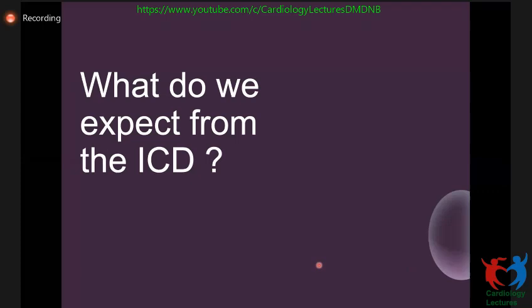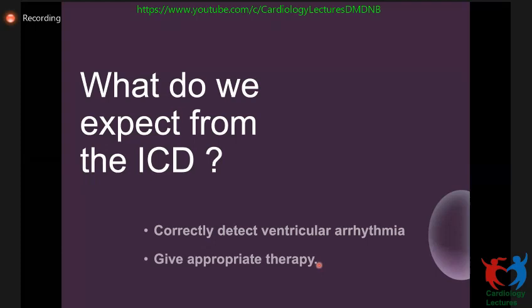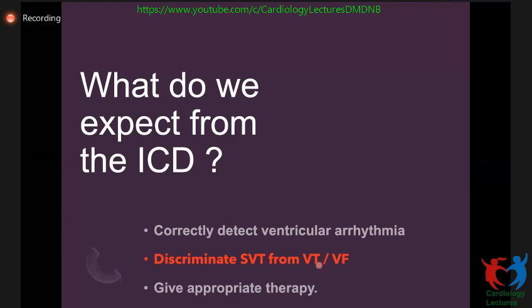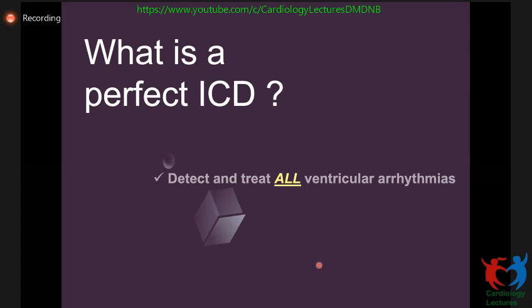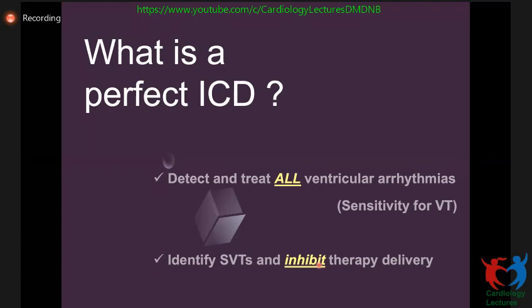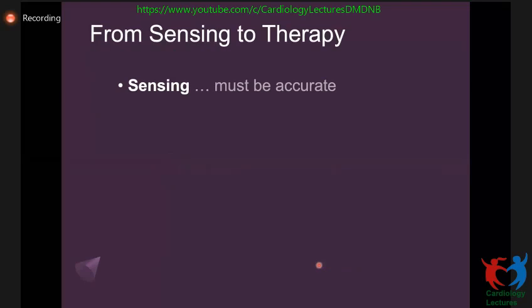What do we expect the ICD to do? We want it to detect ventricular arrhythmia and give appropriate therapies. However, we need to discriminate from SVT because we don't want inappropriate shocks. For the perfect ICD, we aim for detecting all ventricular arrhythmias — meaning the ICD must be very sensitive for VTs — and it should not treat SVT, so it has to inhibit therapy if it's an SVT, requiring specificity for SVT as well.